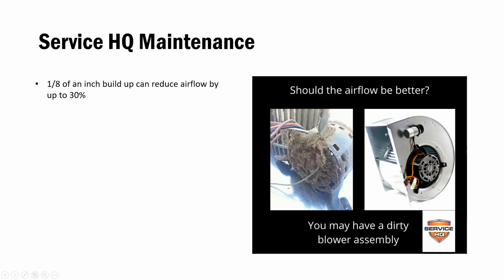And if it is extremely dirty, we do have a charge above and beyond our regular maintenance for that, because it is a lot of work to take all that stuff off, take it completely apart, clean it, put it all back together. It's a lot of extra labor. So it is an extra charge, but it's so important to keep it clean, because just an 1/8 inch of buildup on this blower assembly can reduce airflow by up to 30%. That's going to create some hot or cold spots throughout the whole house. It keeps people from being comfortable, especially on the hottest days. It's just not going to do a great job. So we like to clean them up, make them look shiny again, just like this one.